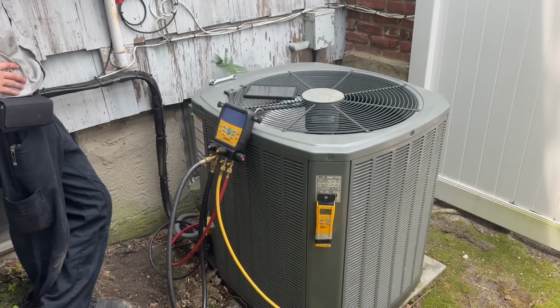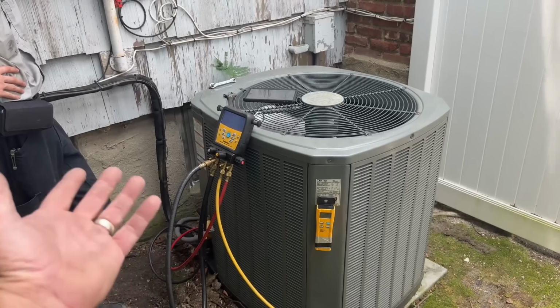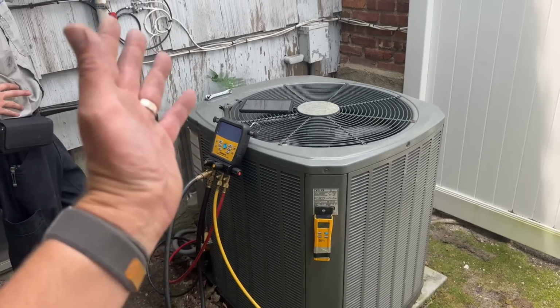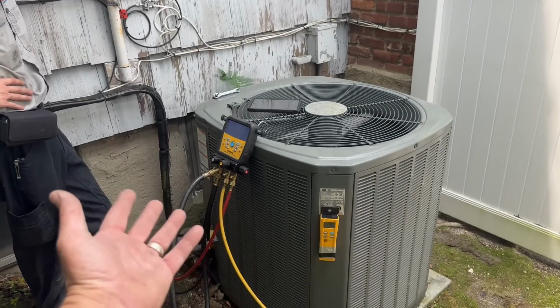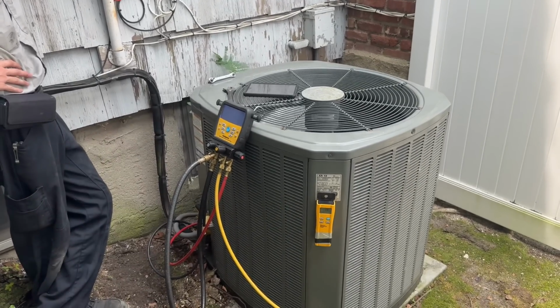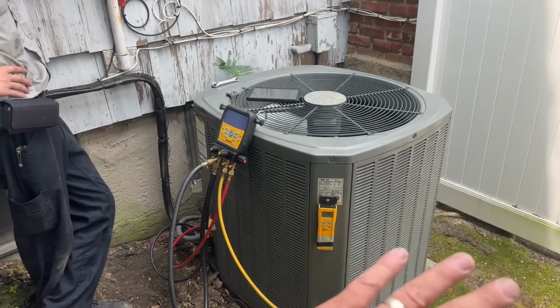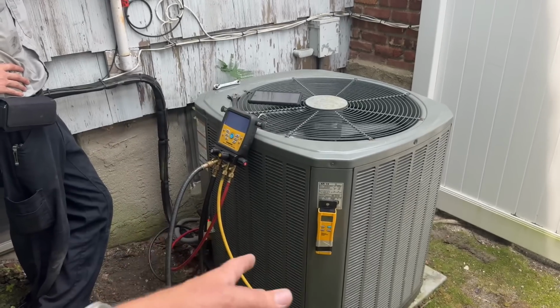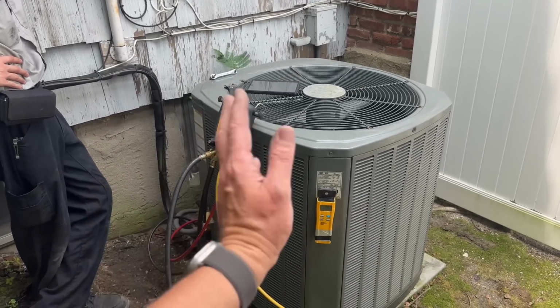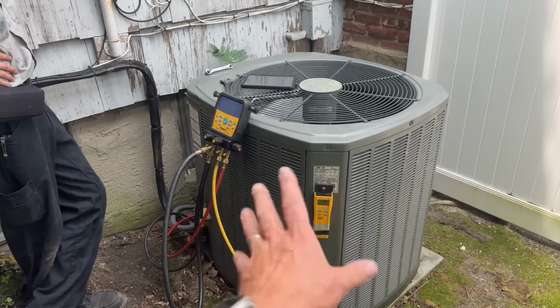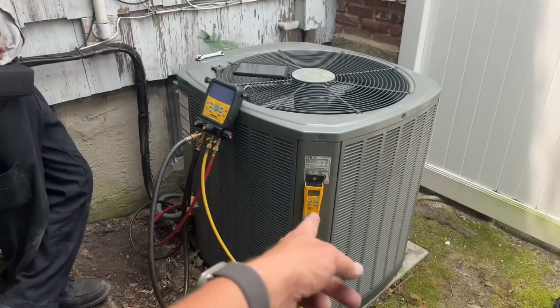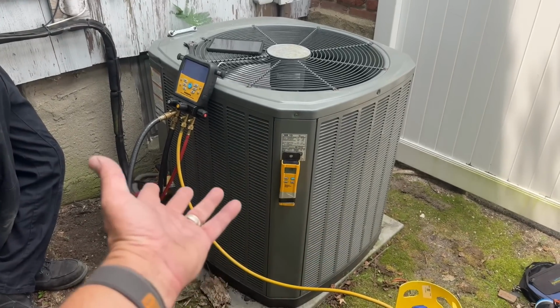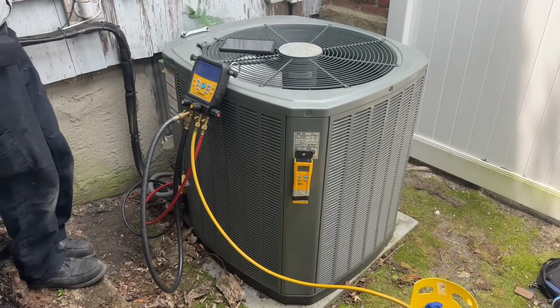So I added 2 pounds of refrigerant, and then I had very high side pressure, almost 500 PSI, and I'm like, all right, we got a restriction in here. Let's stop, we're not going to do anything else. We're going to order a TXV, and now here we are, taking out about a pound, a little over a pound and a half. What did we start at, 1.1? So 1.5 pounds looks like.